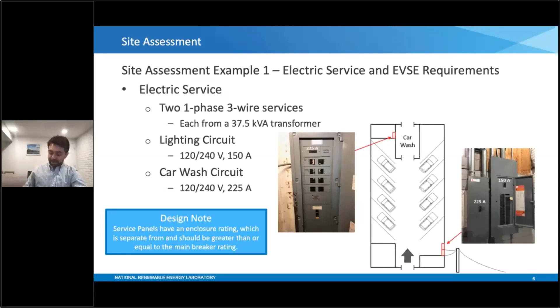A design note: service panels have an enclosure rating which is separate from, and should be greater than or equal to, the main breaker rating. So if we're upgrading main breakers as a result of installing new circuit breakers, you might also need to consider a new service panel upgrade. The benefit of that is you'd potentially get more breaker positions as well, giving more space for future capacity if needed.